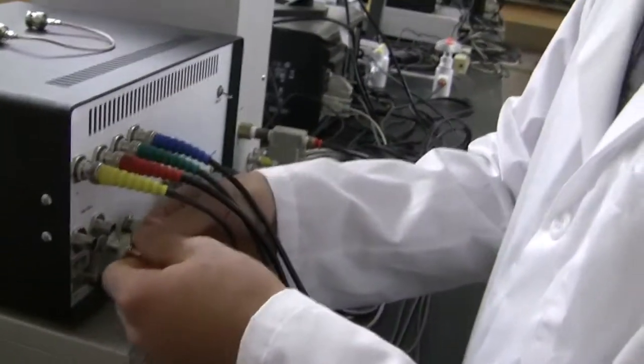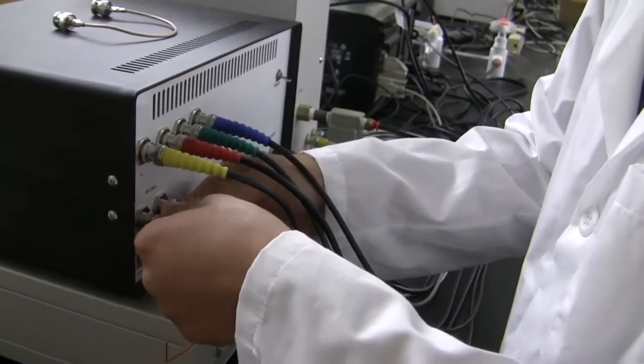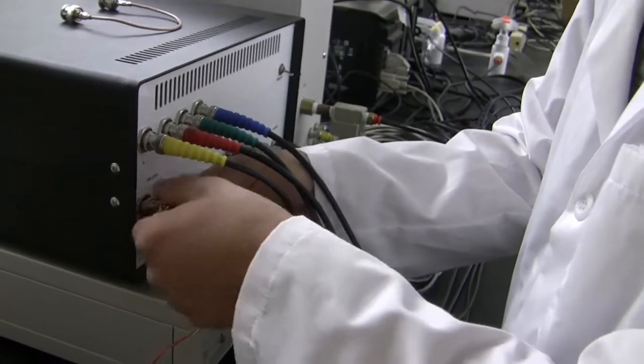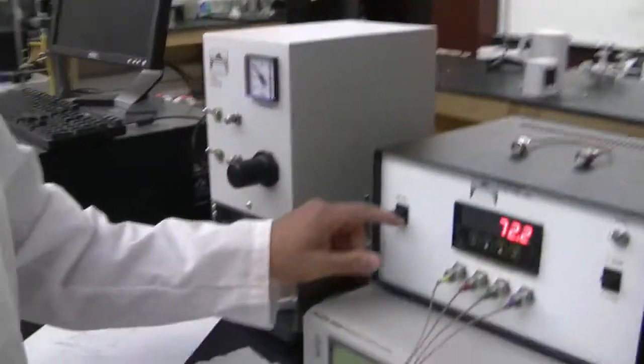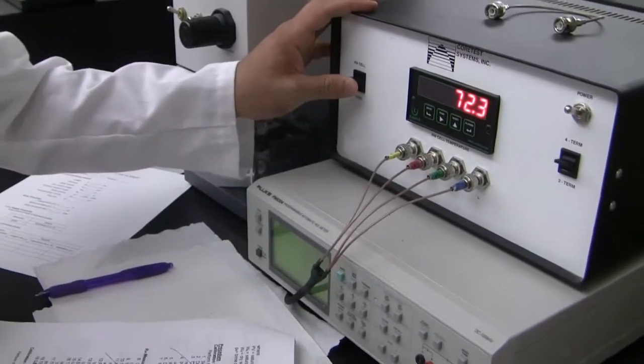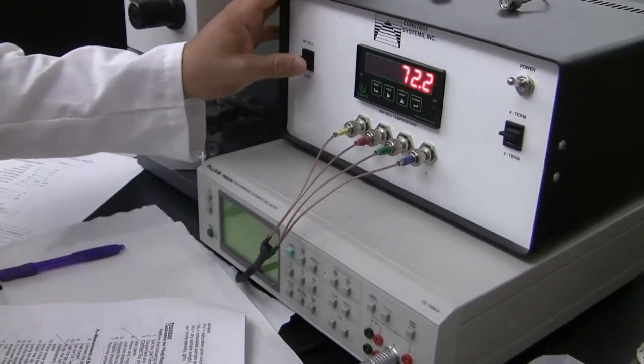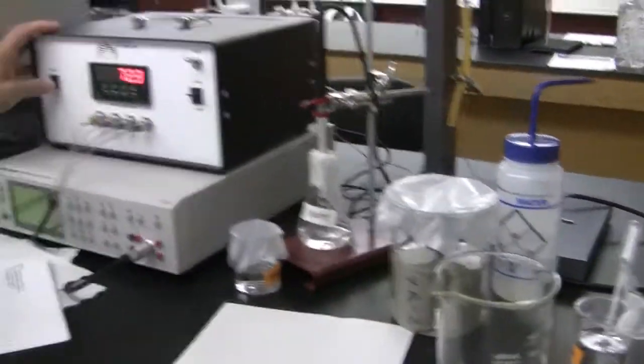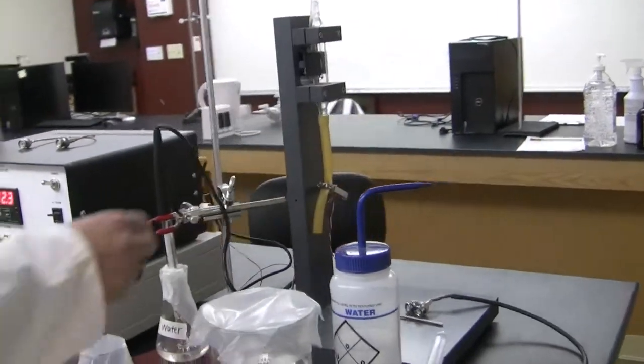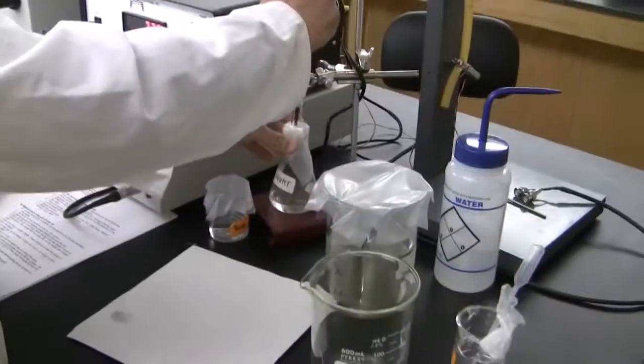This is your dip cell. So you pick back your BNC connectors and connect them again. Go back to the front of your cell. Make sure this is in the same position, RW cell. And then you take the dip cell out of the distilled water, and then you start shaking it to make sure there is no distilled water in there. And then if you are sure it doesn't have any distilled water, you can start dipping it in your brine that you use to saturate your sample, or any brine is fine.